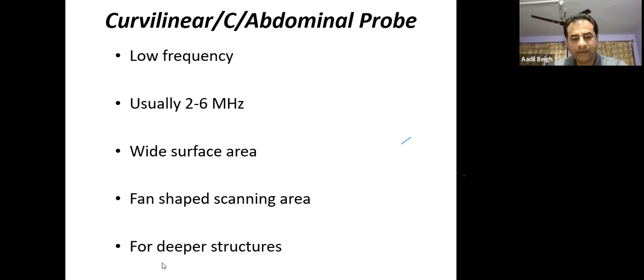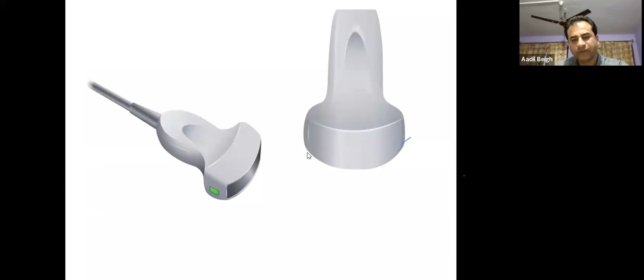There is something written, C568. It means that it is a curvilinear probe, 5 megahertz, and its surface area is 68 millimeters. This is the information we can get from the probe; it's written on the probe. This is the indicator on the probe. This is the area where the piezoelectric material is put. This is the matching layer. This is the case of the probe. It produces a fan-shaped image like this on the monitor. The indicator is on this side, so whatever is on the side of the indicator will appear here.